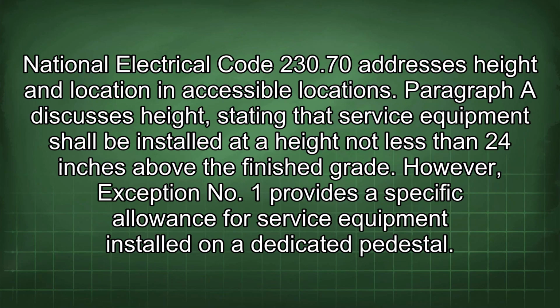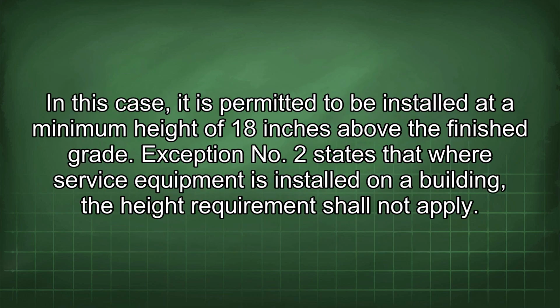National Electrical Code 230.70 addresses height and location in accessible locations. Paragraph A discusses height, stating that service equipment shall be installed at a height not less than 24 inches above the finished grade. However, exception No. 1 provides a specific allowance for service equipment installed on a dedicated pedestal. In this case, it is permitted to be installed at a minimum height of 18 inches above the finished grade.